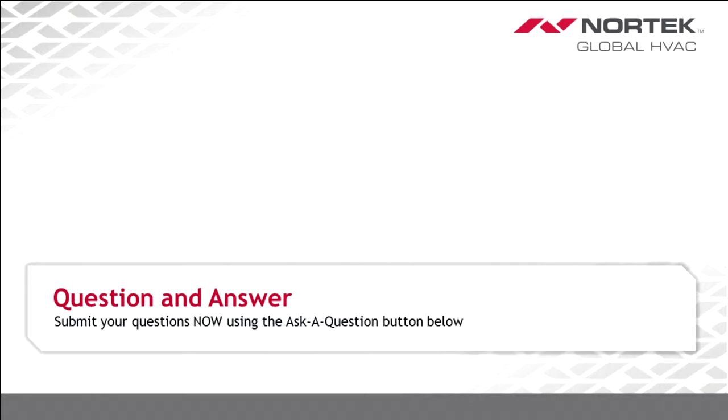Okay. All right. Next one here, Greg. Mike wants to know, do you test and tear down returned units at the factory? Okay, so when the heat exchangers come back loose, in other words, just a heat exchanger, they'll do a visual inspection on them. As far as the quality pledges and stuff like that, when they come back, yes, we do test the heat exchangers and make sure that it was actually a failed heat exchanger or what was wrong with the heat exchanger. So, yes, we do test them.